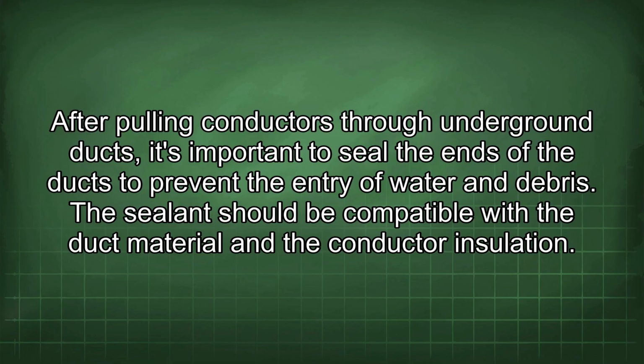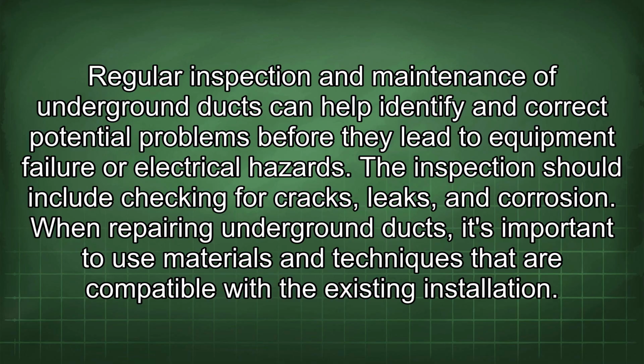After pulling conductors through underground ducts, it's important to seal the ends of the ducts to prevent the entry of water and debris. The sealant should be compatible with the duct material and the conductor insulation. Regular inspection and maintenance of underground ducts can help identify and correct potential problems before they lead to equipment failure or electrical hazards. The inspection should include checking for cracks, leaks, and corrosion.